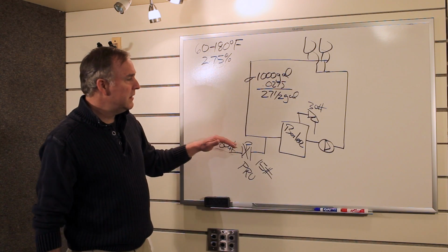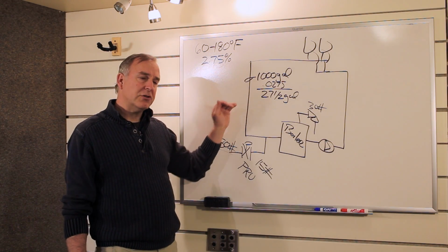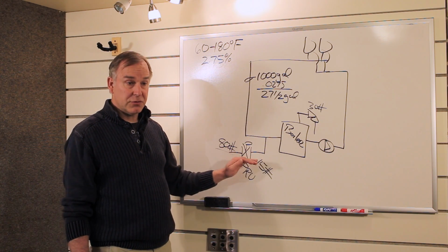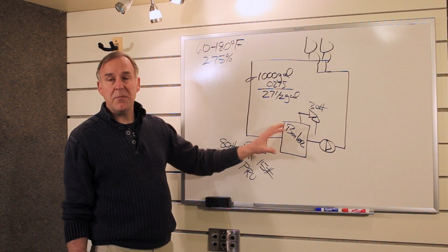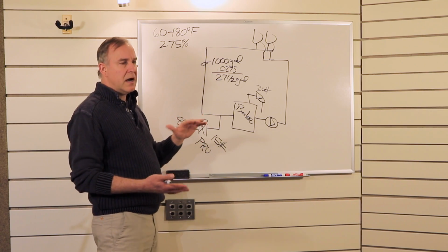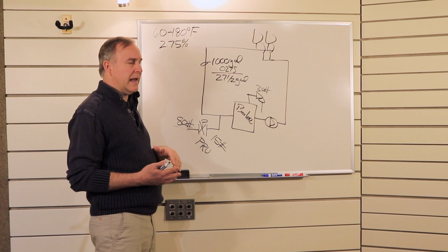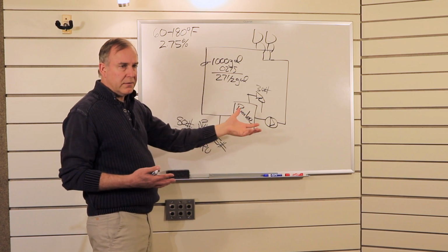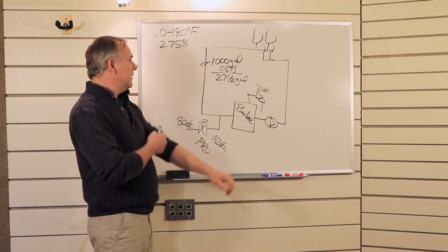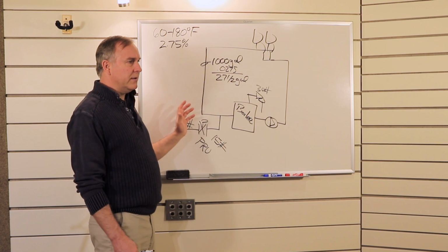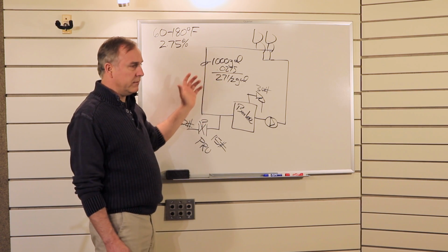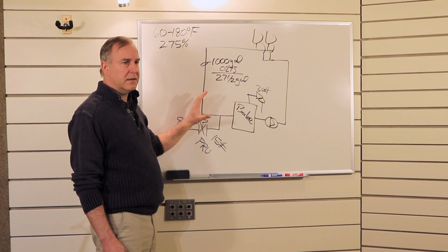So what happens is, as my system cools and my pressure drops, I will feed water in. Once my pressure drops below 15 pounds, I'll start feeding water in, and I'll make up that water that I lost. So as my hydronic system cycles between hot and cold, typically that happens once or so a day, I'll dump water when I'm heating it up and add some water when I'm cooling it down. So literally, I've come up with a scenario here between a PRV and a relief valve where I could really avoid using any kind of expansion tank.